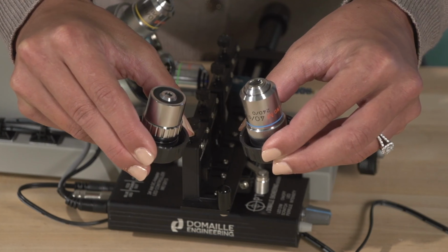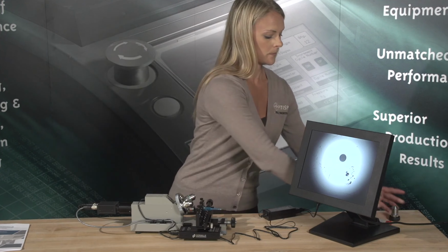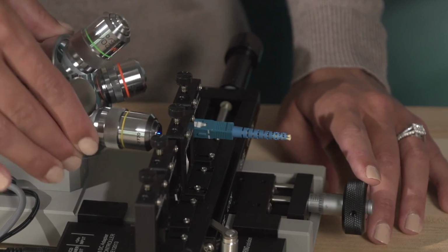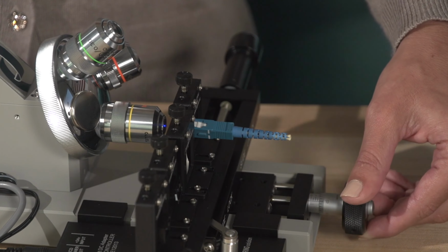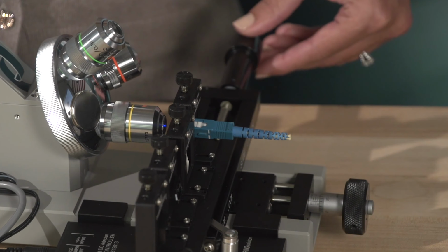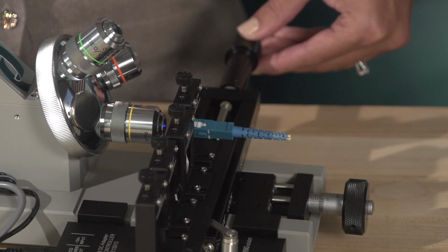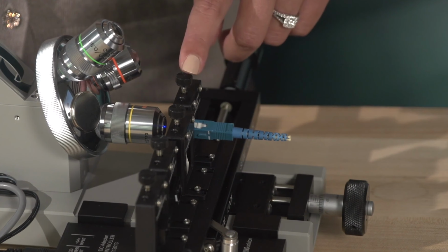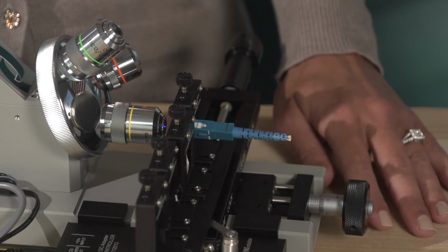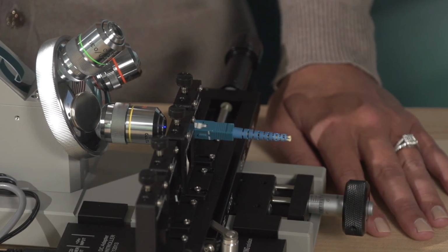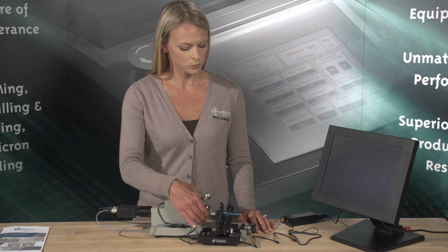Once the image is set up, centered, and in focus using the 5x objective, turn the turret to the 10x position and repeat the focusing procedure. Once in focus, center the fiber using the adjustment knobs on the adapter and linear adapter slide. Repeat again if you desire to view the fiber at other magnifications.